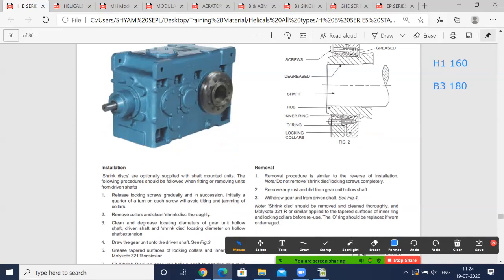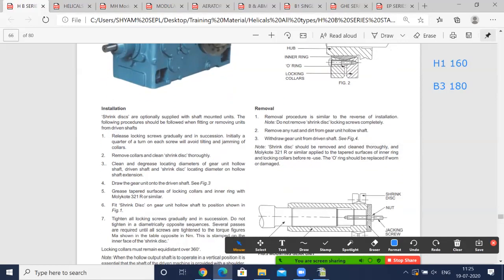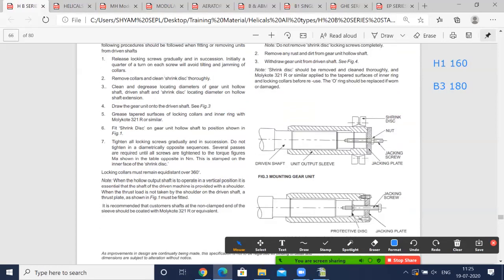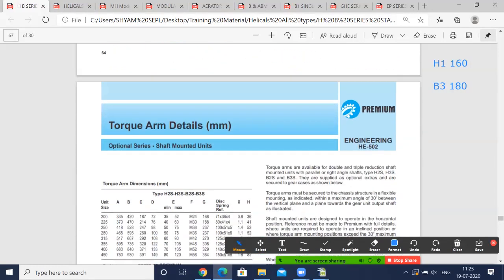So that gives two benefits. One, the pressure or the holding capacity is from all ends, so it helps in giving better torque. And secondly, there is no keyway, so there is no point of maintenance. The keyway won't get damaged. And moreover, in this case, with the shrink disc, you can easily unlock and lock and remove the output shaft. Okay, so it doesn't get fit inside. So these are all points of installation mentioned over here, and you just need to remember them.